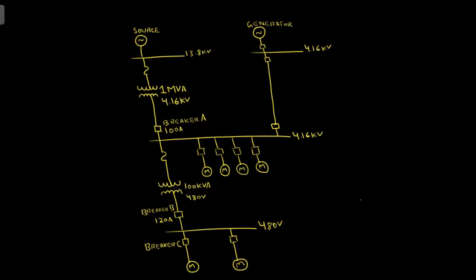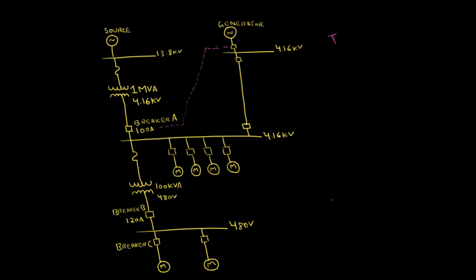Before we talk about intricacies of how coordination is actually performed, let's first understand the general structure of this power system. Under normal operating conditions, the tiebreaker connected to the generator bus would be open and interlocked as the system is powered by the utility bus through the utility transformer.